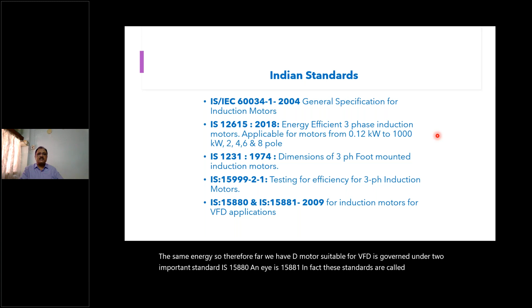And when a flow is altered, pressure is also altered and the power is also altered. So in that sense, VFD offers an excellent opportunity to optimally operate the process machines as well as save energy. Therefore, motors suitable for VFD are governed under two important standards, IS 15880 and IS 15881. In fact, these standards are called the guide for selection of induction motor when fed from VFD applications.